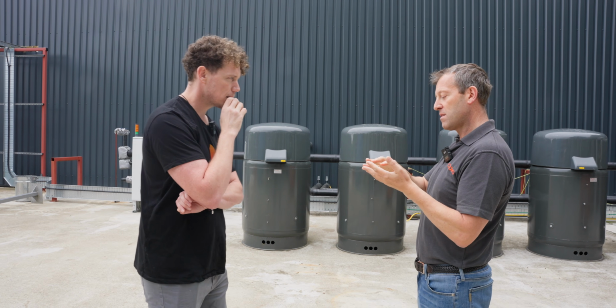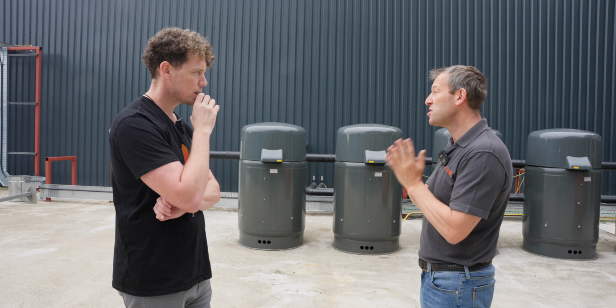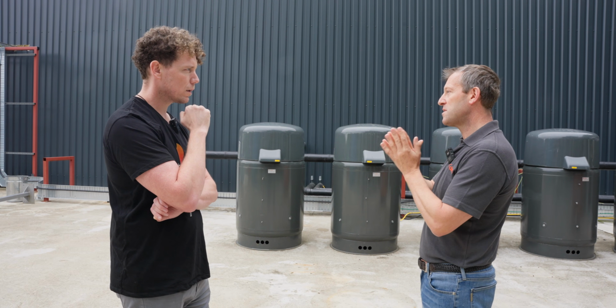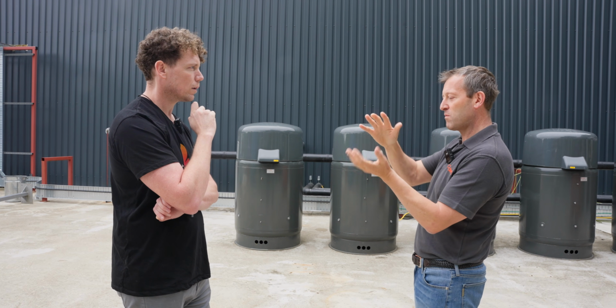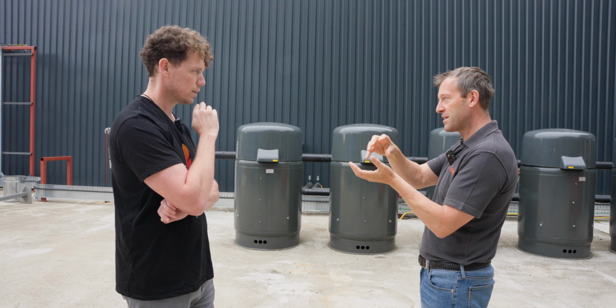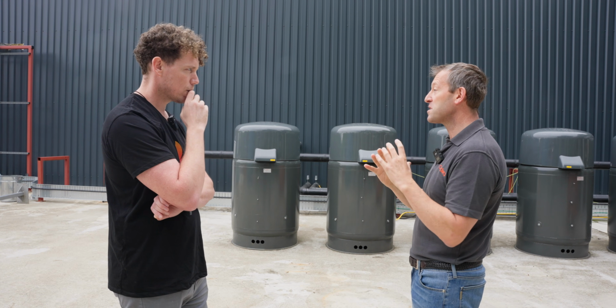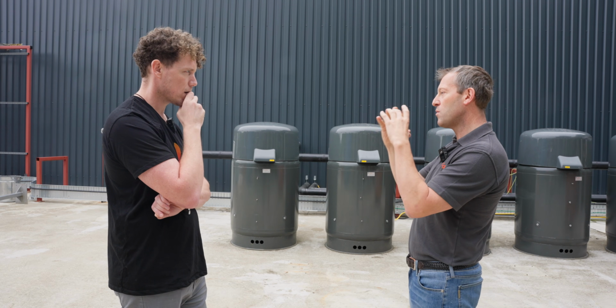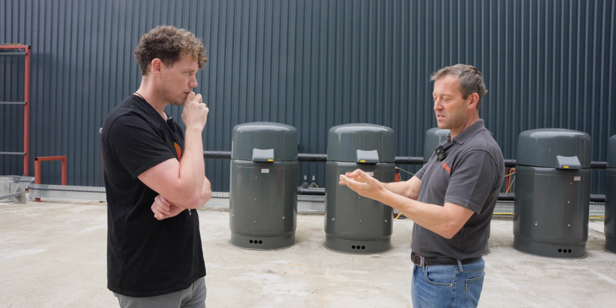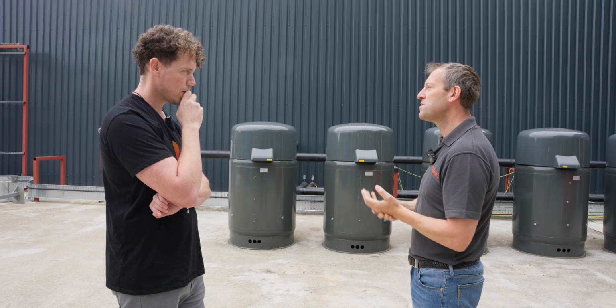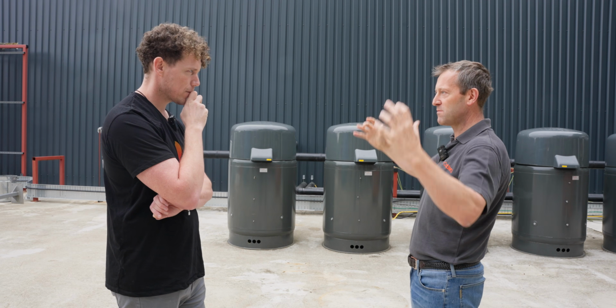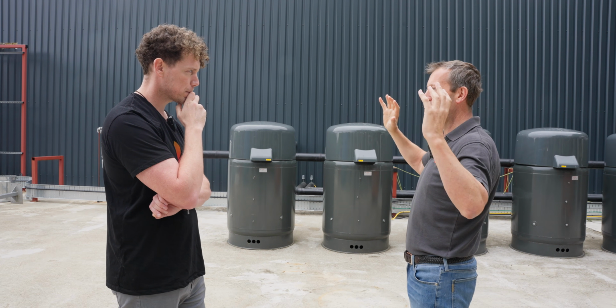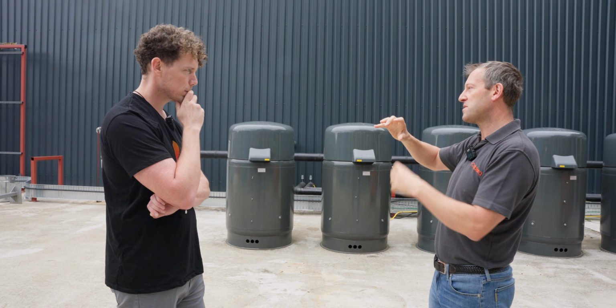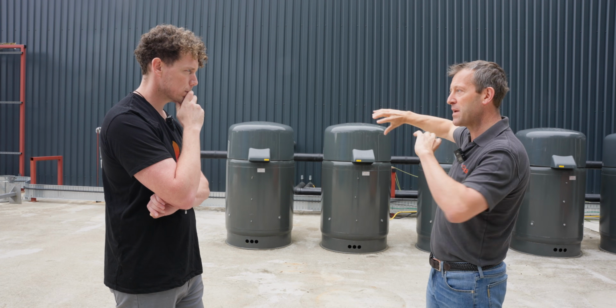The third reason is that it's also the cheapest way of moving heat around. Because of the energy change from going from a liquid to a gas and back again, the pipes are much smaller than if you did it with hot water. So you find in a lot of factories, hospitals, and industries, they just use steam heat. They have these big boiler houses with great big boilers burning gas 24 hours a day, generating steam and pumping it all around the site in these big pipes.